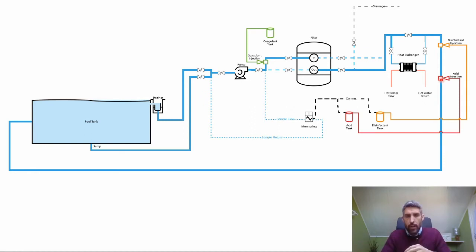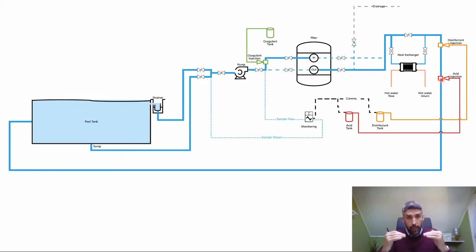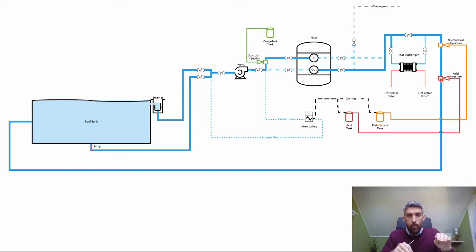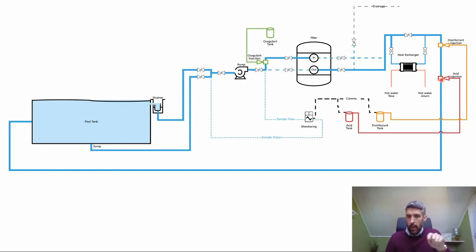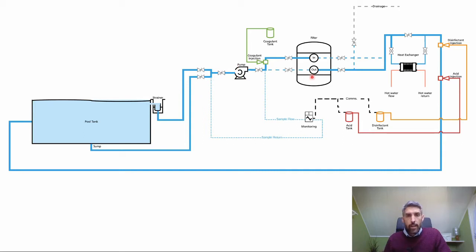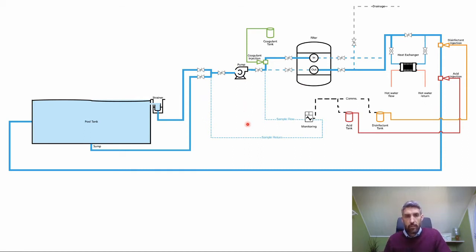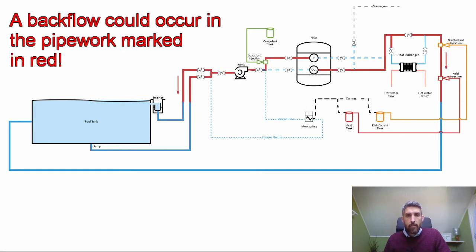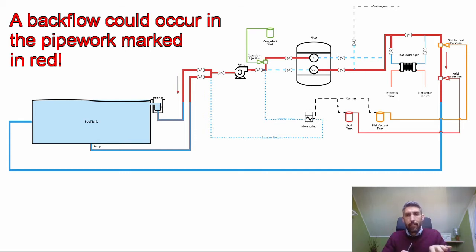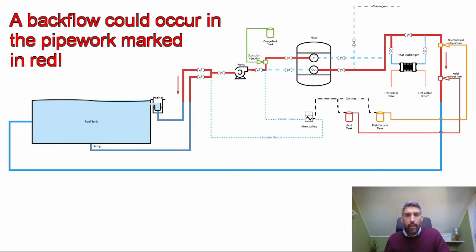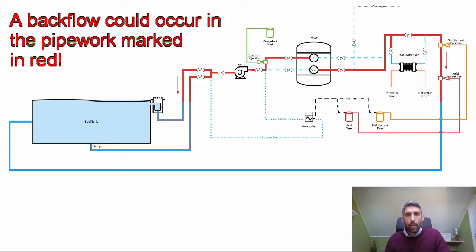But sometimes you get situations where all of this equipment—the pump and the filter—are above the level of the pool. It's not too bad when the circulation is going, but you won't have a problem necessarily until that pump stops working either through fault or through doing a backwash. What will happen is if you look at the red pipework now, all of that stuff that was above the level of the pool, you're going to potentially get a backflow of water draining back.